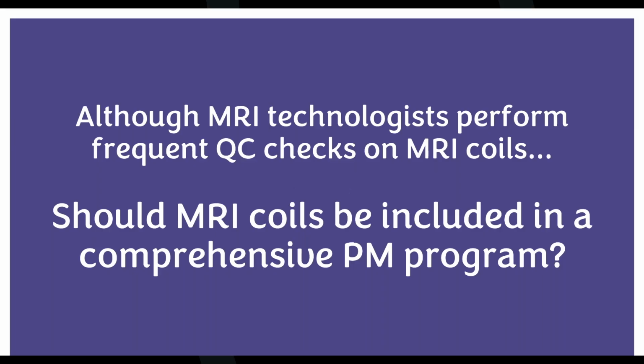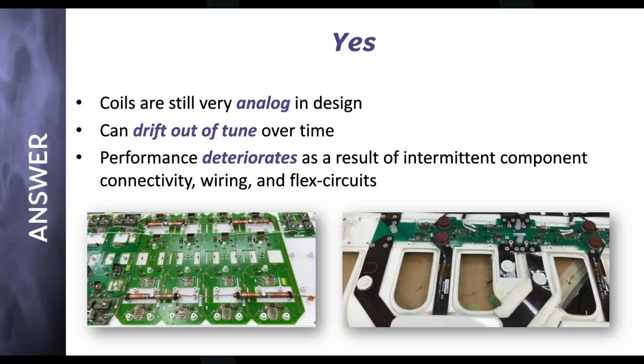Perfect. Although MRI technologists perform frequent QC checks on MRI coils, should MRI coils be included in a comprehensive PM program? Yes. You are correct. They are very analog in their design, but because of that, they can definitely drift out of tune. And I think in more cases than not, they are not part of a PM program. The performance will deteriorate over time, and many of these coils are in use for a long period of time.